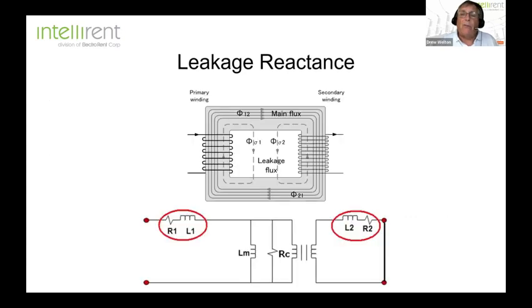Now, what are we actually doing? Well, we're looking for leakage flux. That's why we call it leakage reactance. Flux measured in terms of impedance of the transformer. Let's take an example. Let's say you have a wooden trough running downhill, and there's water in the trough and it's flowing downhill, and naturally from top to bottom you'll have a little bit of that water spill out, and that'll be your leakage. Well, a transformer has a certain amount of normal leakage flux within the core and the windings. Well, let's say you take a rock and you put it in the middle of that trough. You're going to have a lot more leakage, aren't you? And that's the same thing.